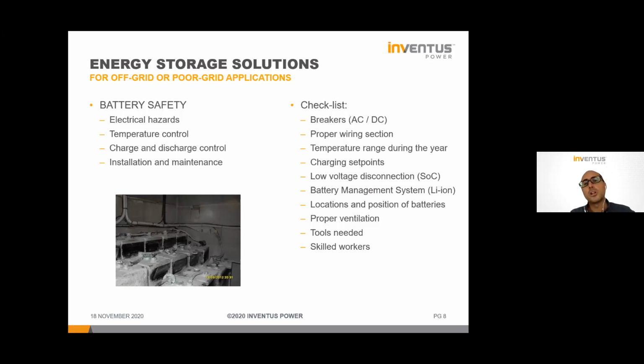We install batteries with some distance between them so air can flow between the battery cells, for better thermal conditions as well as ventilation. Here's a picture of a non-ventilated area where batteries released a lot of hydrogen, and high concentrations of hydrogen can be explosive. So we need to remove that hydrogen from the battery room through proper ventilation.